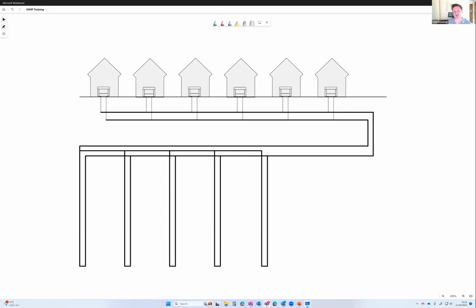Now let's look at this example where we've got 6 dwellings or 6 commercial buildings connected to a single loop. What we can take advantage of is assuming not all these buildings are running at the same time - diversity on the heat network. It's akin to plugging in a 4-way electrical adapter: you wouldn't assume you're going to have a 13 amp electrical fire on each one. That just wouldn't be reasonable. So it's analogous to that.